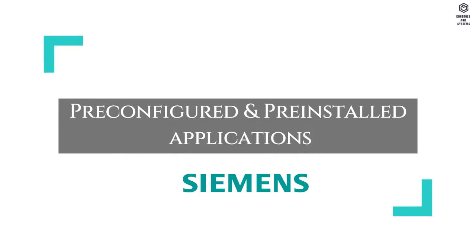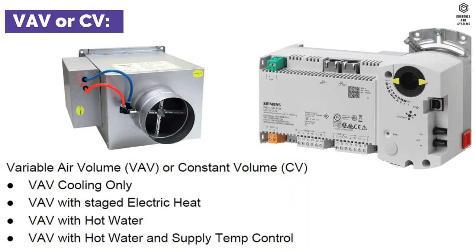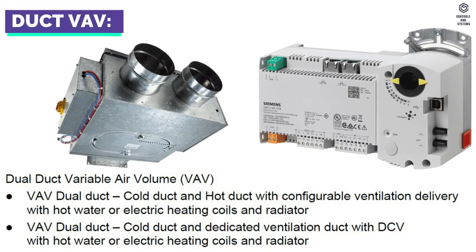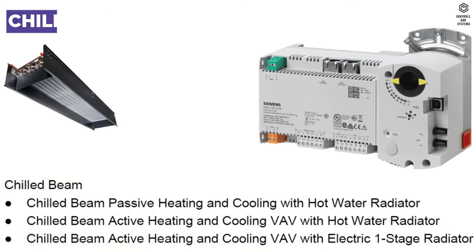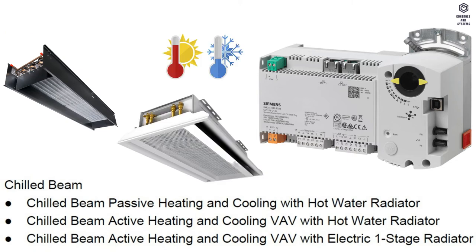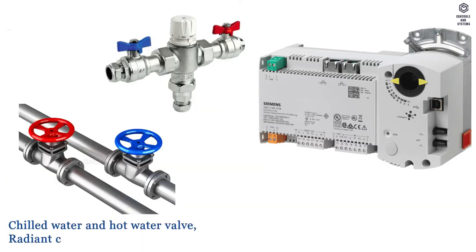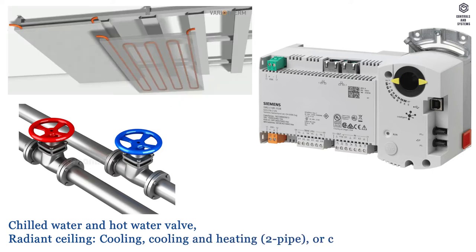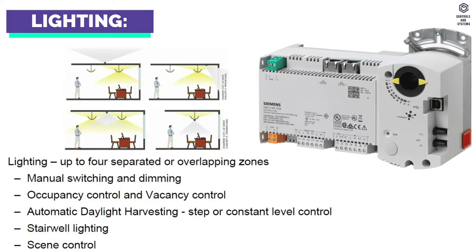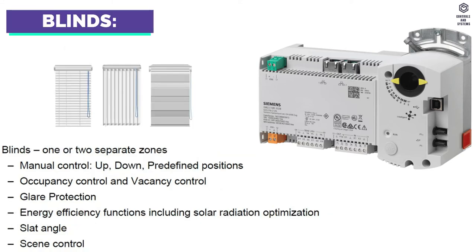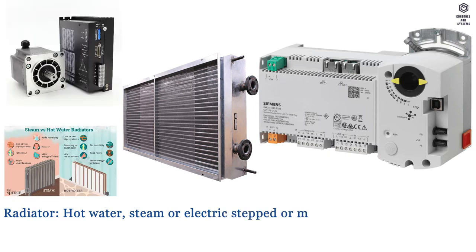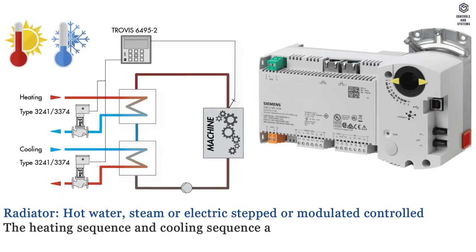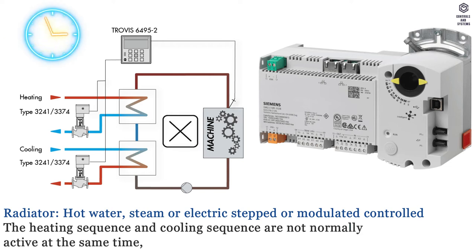Pre-configured and pre-installed applications include: variable air volume or constant volume, dual duct variable air volume, fan powered boxes, chilled beam for passive or active heating and cooling, chilled water and hot water valve, radiant ceiling for cooling and heating, light up to four separate zones, blinds with one or two motors, and radiator with hot water, steam, or electric stepped or modulated control. The heating sequence and cooling sequence are not normally active at the same time.